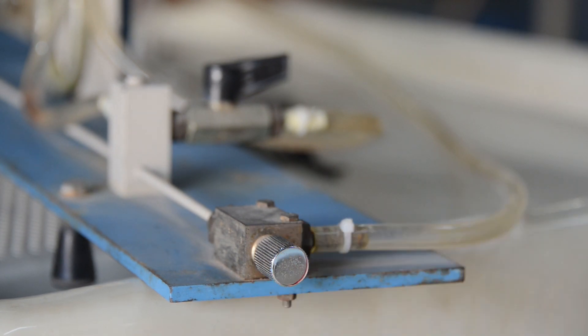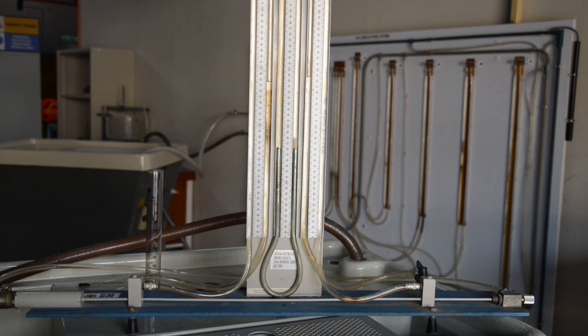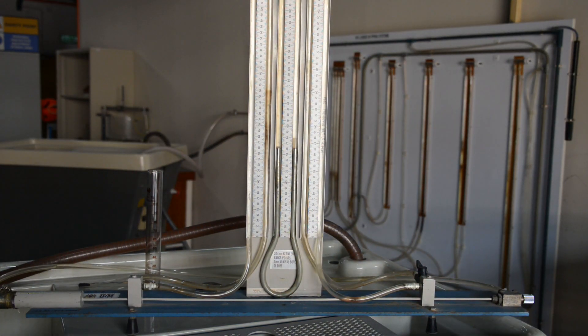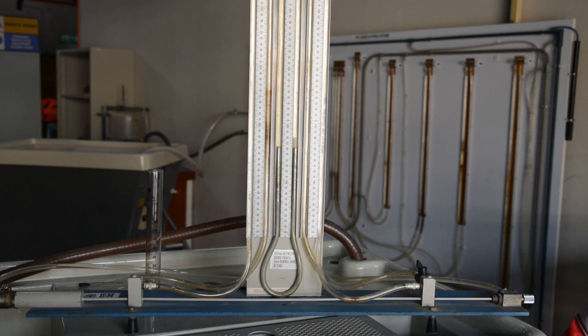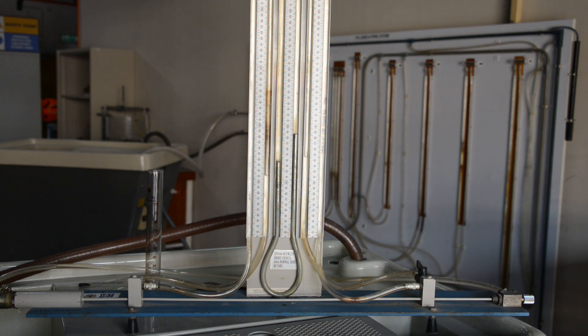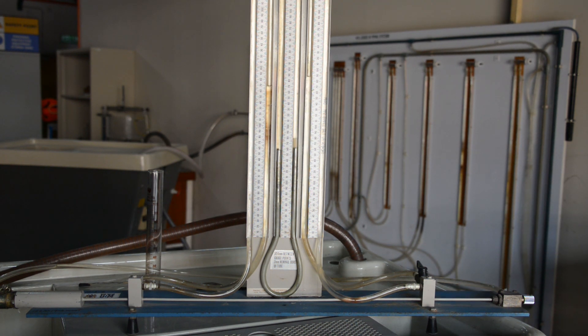The water and mercury level in manometer tube will start to move up and down. This is referring to the changes of pressure at minimum flow rate. If the manometer level is not moving, please release the air trapped in manometer tubes by using bleed valve.